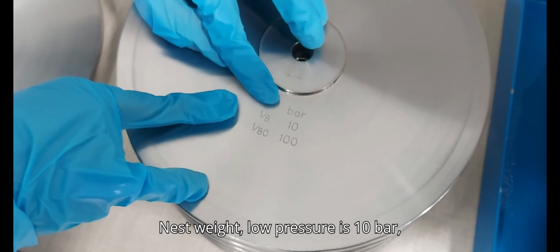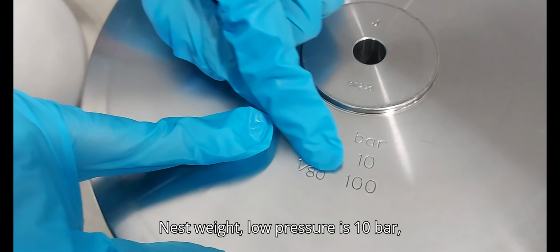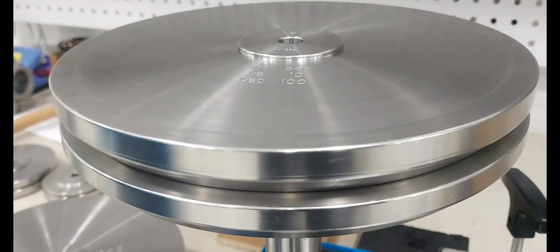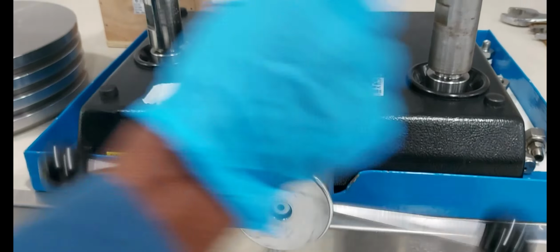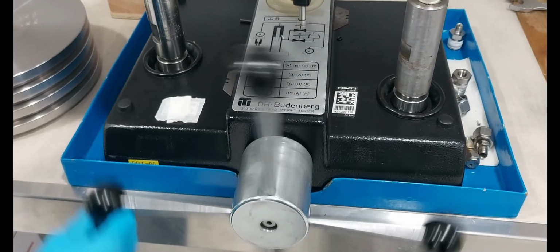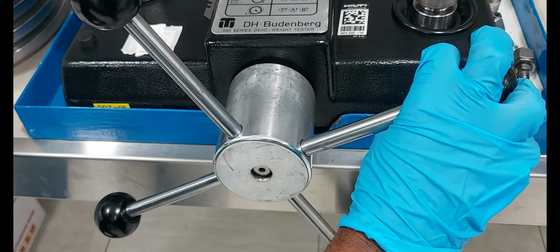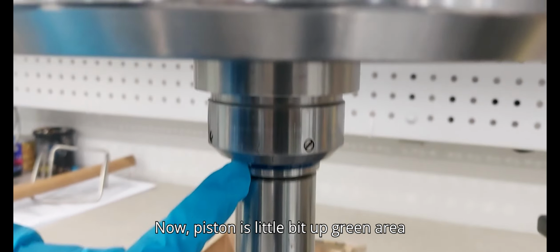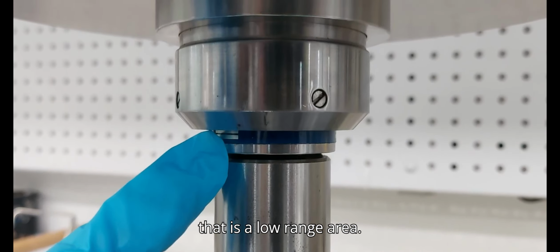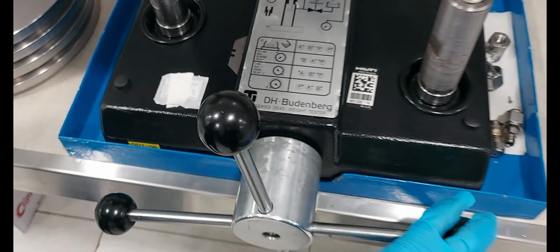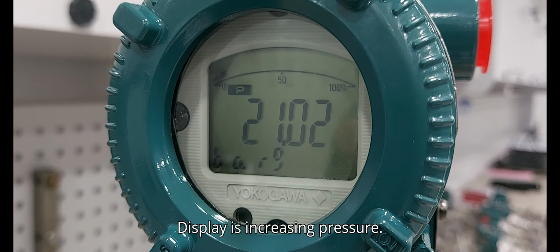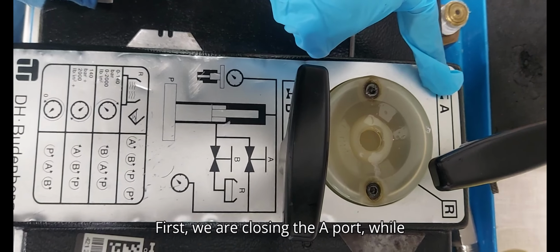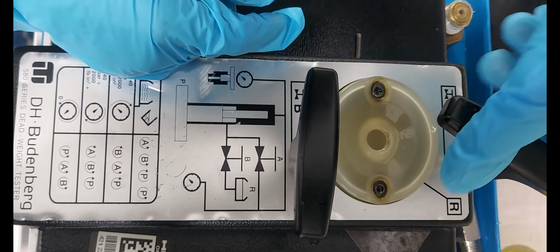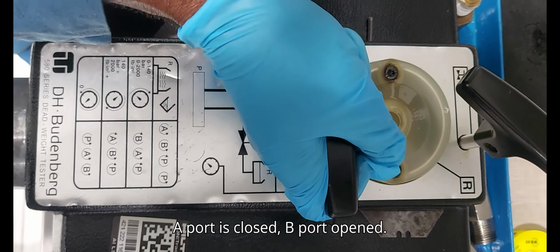Okay. Next weight, low pressure is 10 bar, high pressure is 100 bar. Next we insert the weight. Rotate the screw pump. Now the piston is a little bit up, in the green area, that is the low range area. The display is increasing pressure. Next we are closing the A port valve. A port is closed, B port open.